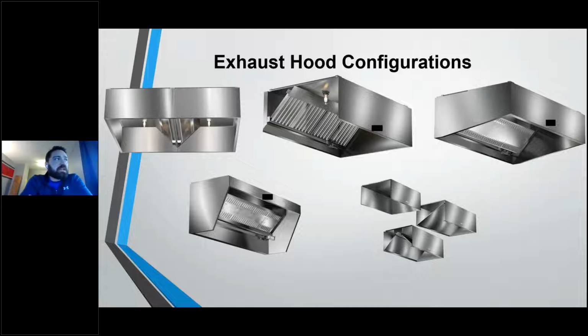When I get to this part of the presentation, I'll inevitably have somebody thinking, "Hey, Mike, you're missing a hood configuration," and that hood configuration is your traditional island canopy hood, which are definitely still out there in the marketplace. But due to cost, what we have been seeing more and more across the industry, and the hoods have been proven to work, is wall canopy hoods in island applications. So that would be a wall canopy hood with a finished back hung over, say, an appliance in an island application. And what I've typically seen is that the capacity or the CFM of those hoods is typically increased by about 20% to account for the added space around the hood and the added potential that people are walking around this hood and negatively affecting capture.